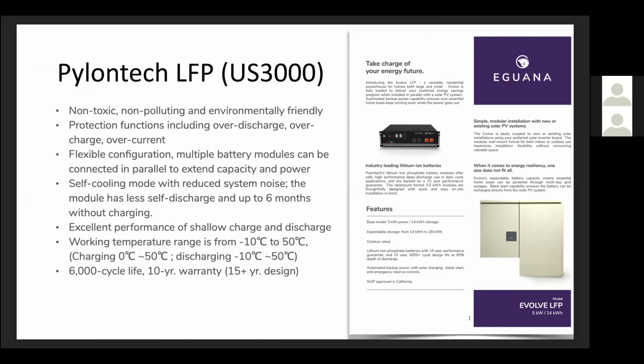A quick look at the Pylontech LFP battery modules. The LFP is a lithium iron phosphate. It's non-toxic, non-polluting, and environmentally friendly. There's a much higher percentage of recyclable materials within this version of the product. Protection functions include over discharge, overcharge, overcurrent, kind of basic stuff for most batteries. It does have a flexible configuration. Multiple battery modules can be connected in parallel to extend capacity and power.